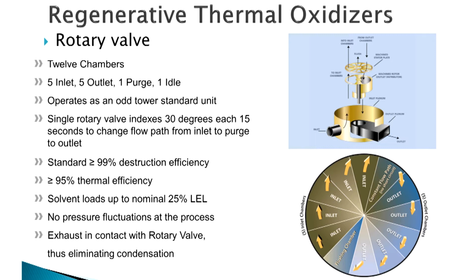The really attractive thing about this particular device is because of the multiple pi sections and the limited movement of the valve, we get very, very little pressure translation back on the process. And so for processes that are very, very sensitive to pressure upsets, an oven that could puff, or a coater that could puff blue smoke, this becomes favorable to that situation.